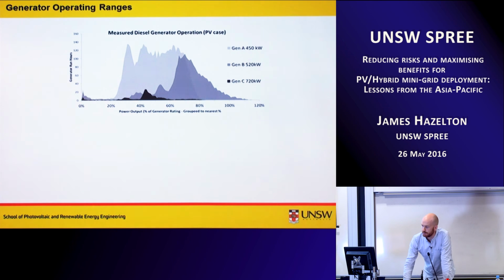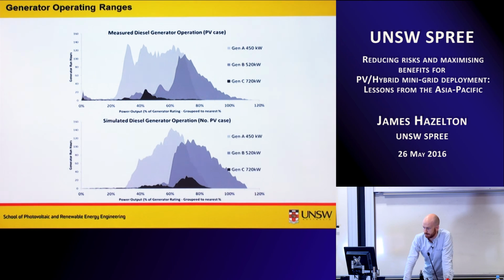What we could do with ASIM, in the no-PV case I modelled before, is represent how the system operated beforehand. It's still not ideal, mind you - there's operation below 40% - but this is more typical of how a diesel generator supplier would say you should operate your system.